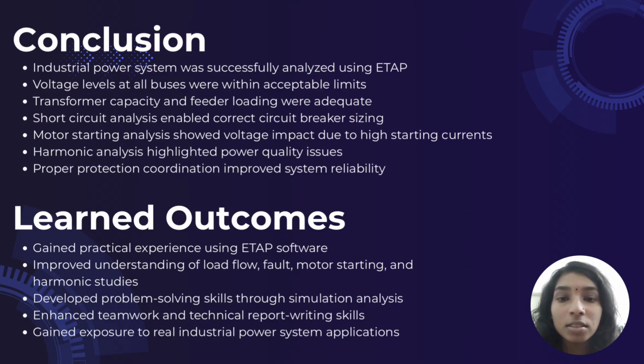Motor starting analysis showed the impact of high starting currents on system voltage, highlighting the importance of considering motor starting conditions during system design. Harmonic analysis identified power quality issues, emphasizing the need for harmonic assessment in modern industrial power systems. Proper protection coordination ensured selective fault isolation and improved overall system reliability.